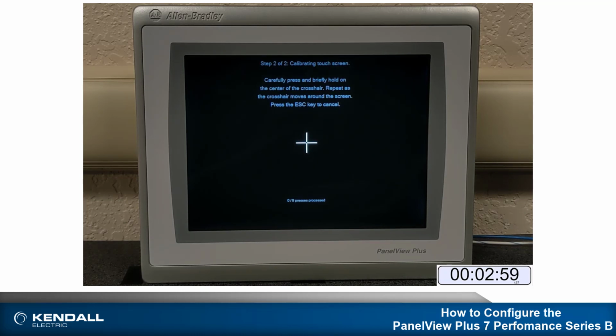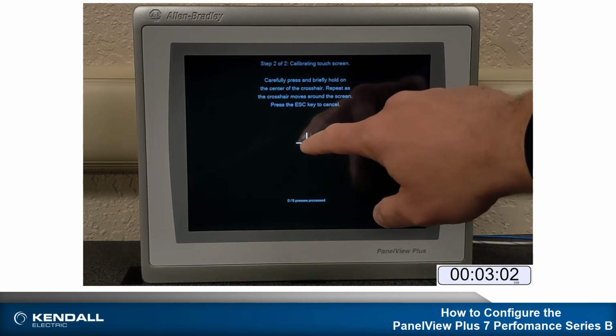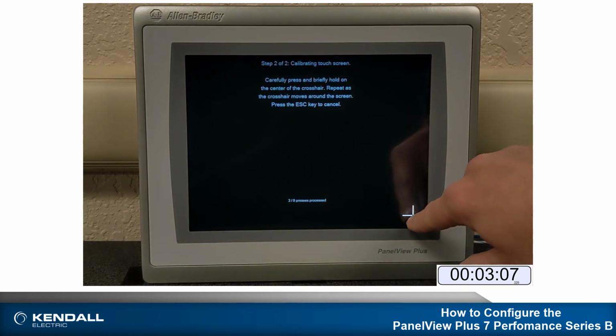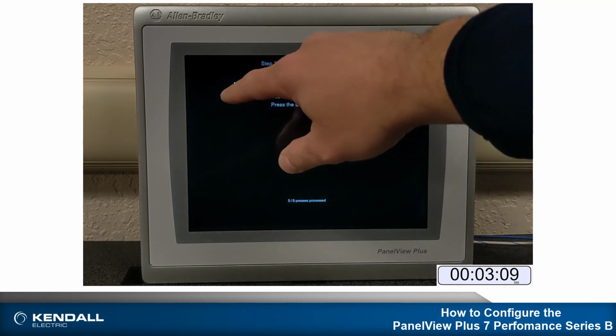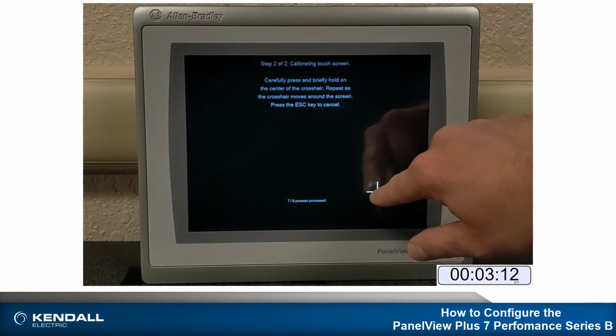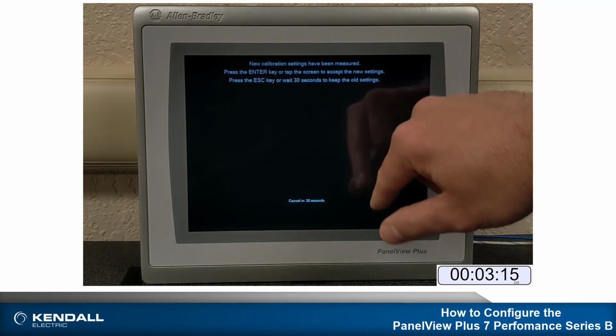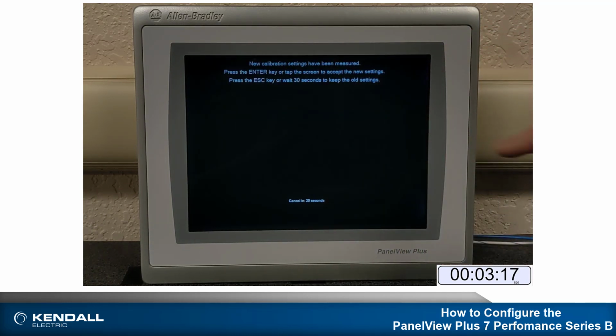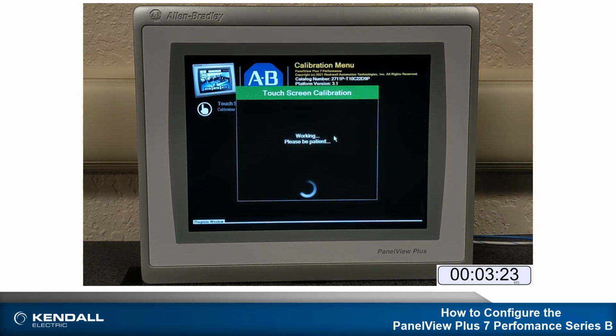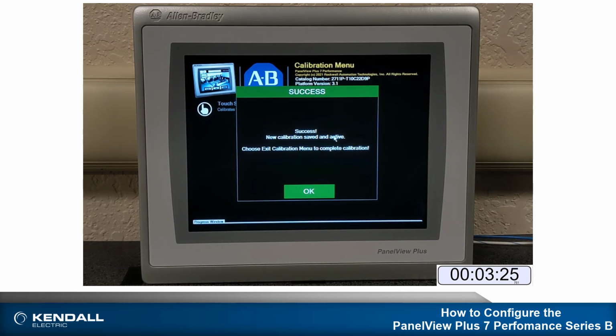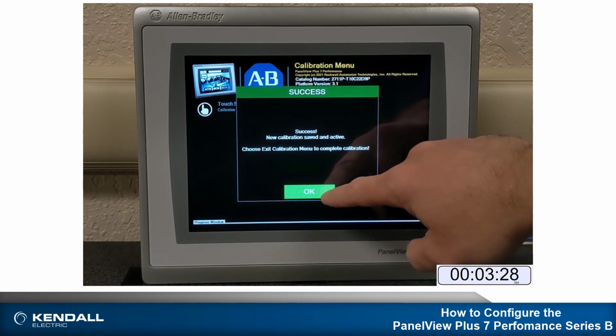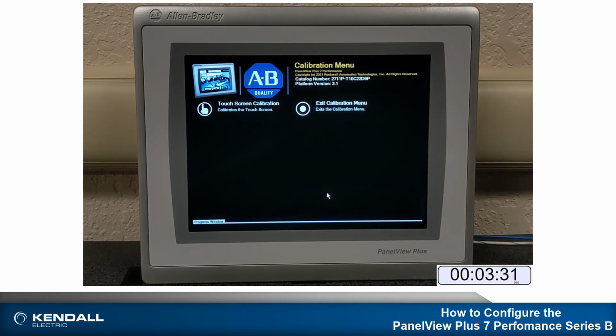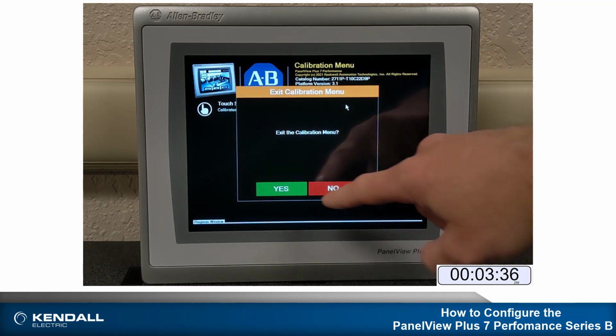The next step will be to calibrate the touchscreen by carefully pressing and briefly holding on the crosshairs as they move around the screen. We will do this in 9 different locations. Once this is completed, we can touch the screen to accept the new changes and save the calibration. Once successful, we can save and press the OK. Now the calibration is complete, we can go ahead and exit the calibration menu and choose Yes.